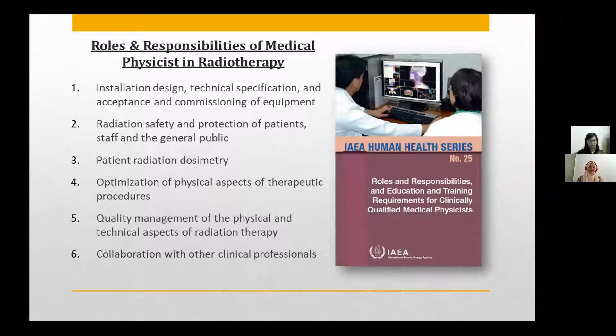First, installation design, technical specification, and acceptance and commissioning of equipment. So the medical physicist is an essential part of the team for the installation design and shielding of new or modified radiation therapy rooms, ensuring that safety requirements are complied with. So this is a typical LINAC room layout, the design, where this is a primary barrier for the primary beam. So medical physicists have to verify the adequacy of the shielding after installation.